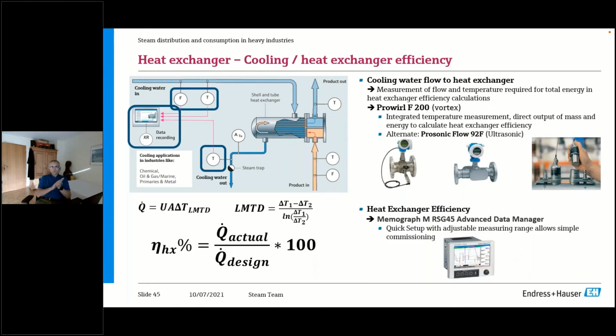Just a side remark for cooling applications, this is pretty similar. You would want to know the energy in versus the energy out, so you then can calculate the heat exchanger efficiency. And this energy calculation, energy out versus energy in, is actually more accurate than just using UA values and the delta temperature. So this is a clear recommendation.